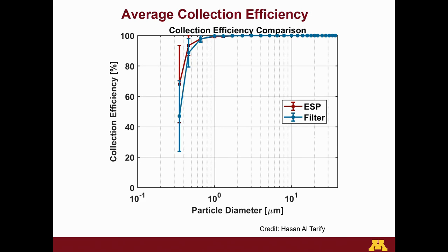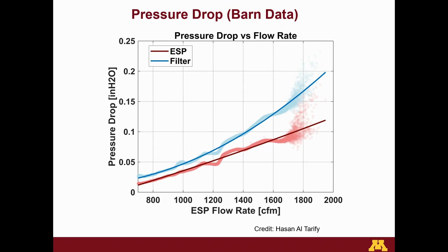This is a composite, or a summary, I should say, of all those previous collection events, showing the fractional efficiency or collection efficiency by particle size for both the ESP in the red and the filter in the blue. So that's the collection efficiency portion of this. Nothing really surprising, and we'll go through what that efficiency is on a MERV 14 in just a bit. Through the pressure transducers, we're able to measure the difference in pressure drop inside each of those filter boxes. And as expected, we have a lower pressure drop with the ESP than the filter.